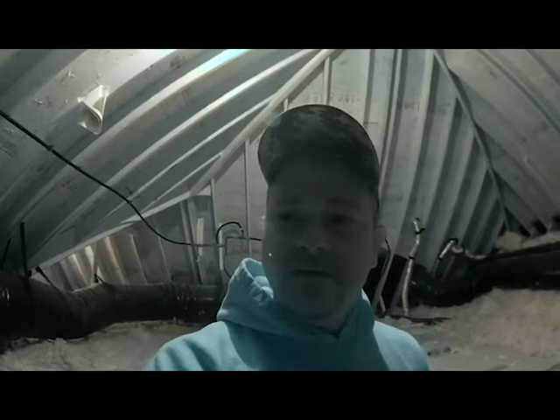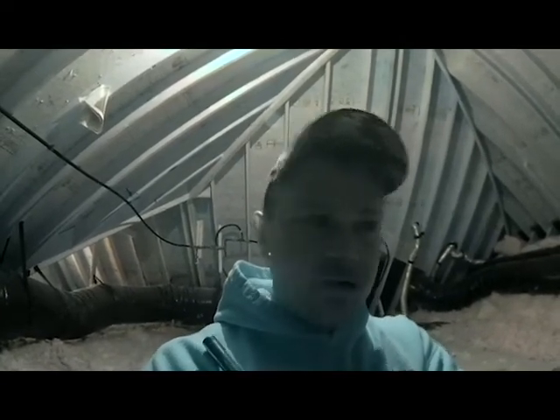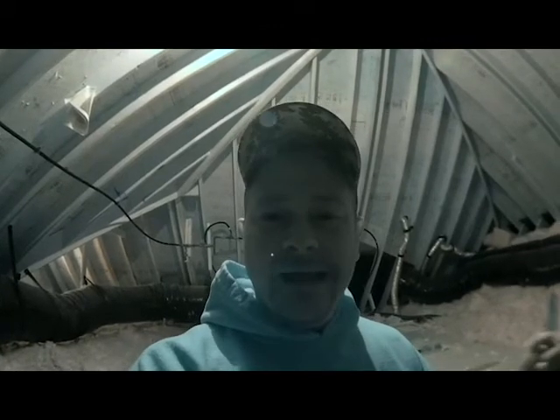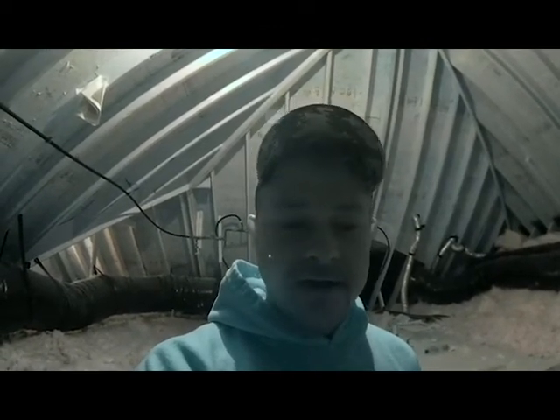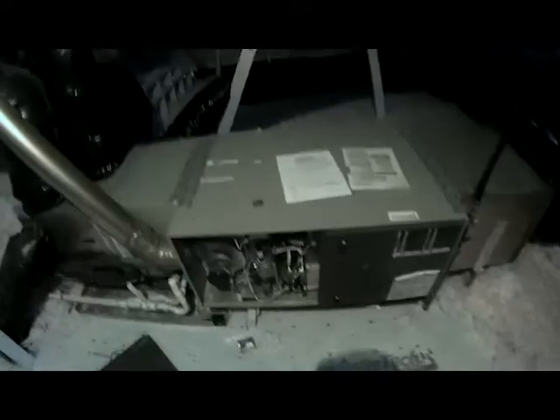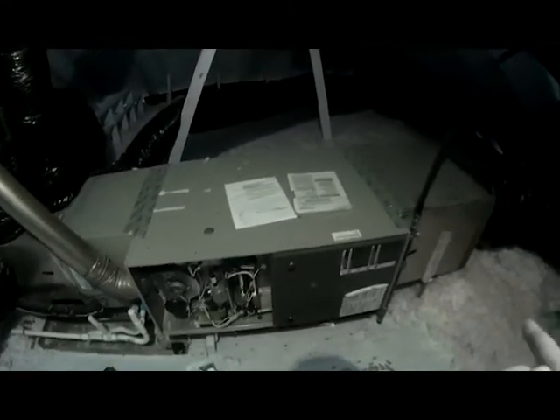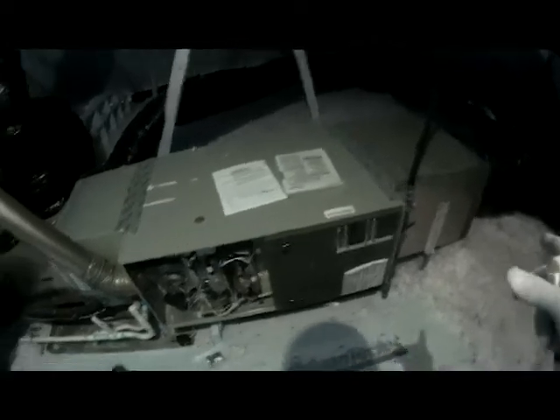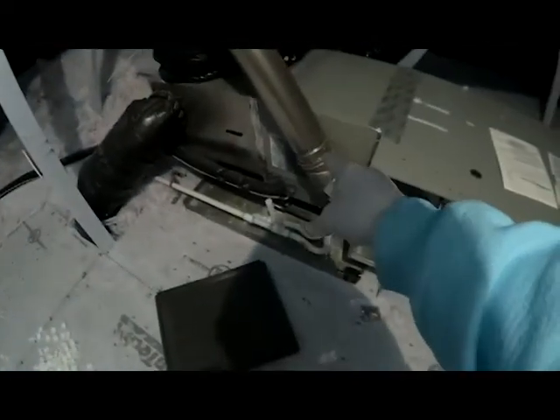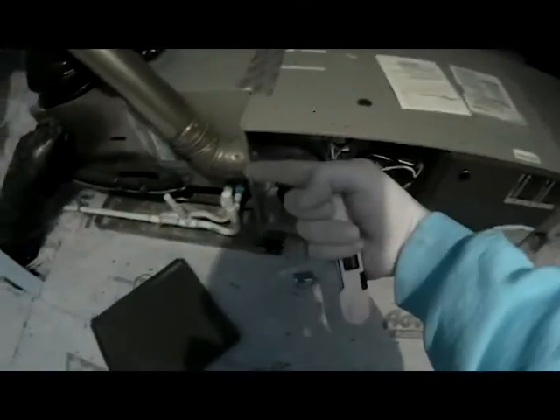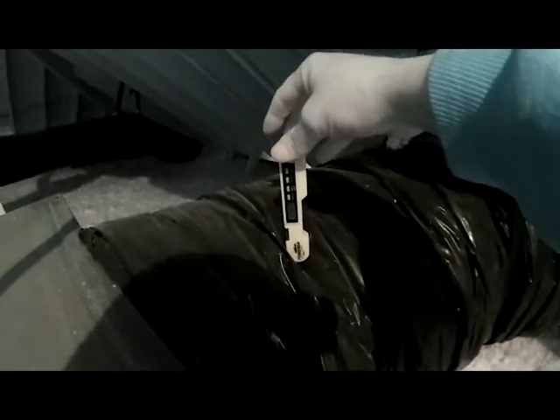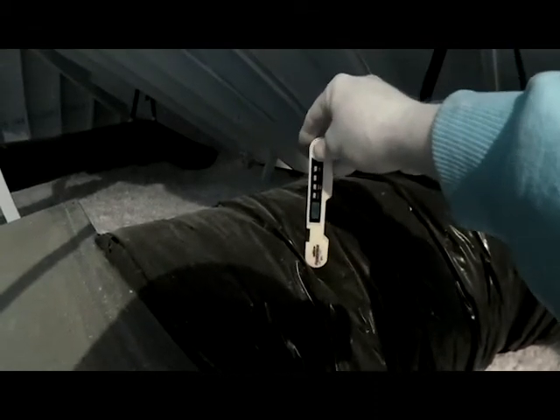Now, how we get that is we need to measure the temperature in our return and our temperature in our supply, and the difference between them will be our temperature rise. So let's go ahead and measure this on this furnace. First we need to find the return of this system, and we can see the evaporator coil is here, so our airflow is actually going this way. So the ductwork over on this side will be our return, and this will be our supply. We're going to take a temperature probe and stick it right here in our return duct to measure our return temperature.